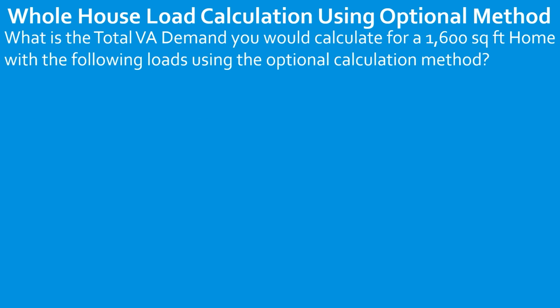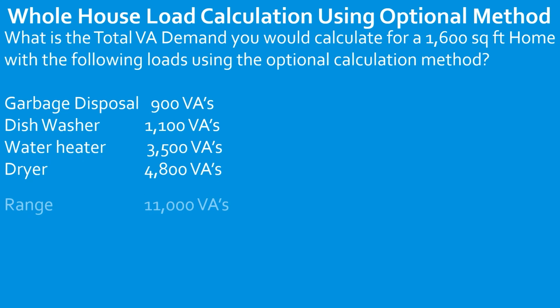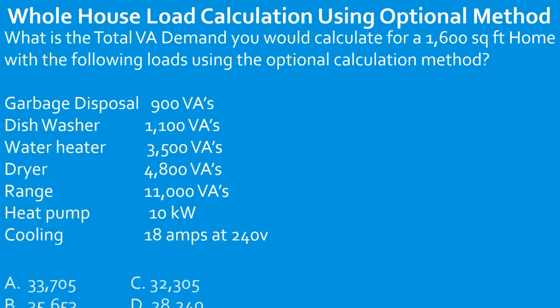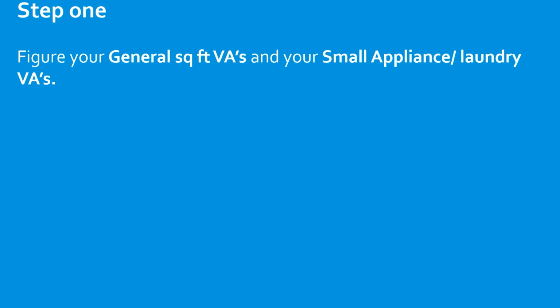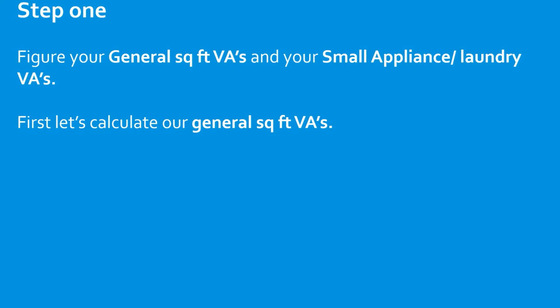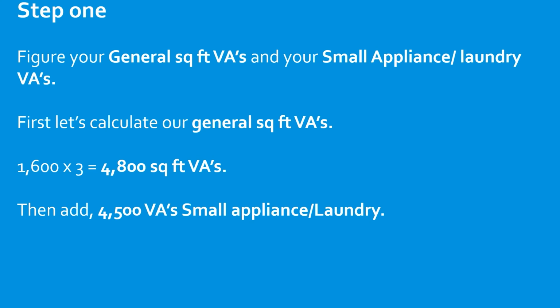What is the total VA demand you would calculate for a 1600 square foot home with the following loads using the optional method? Garbage disposal, dishwasher, water heater, dryer, range, heat pump, cooling, and we've got some options. Step 1, you always figure your general square foot VAs and your small appliance laundry VAs. First, do your general square foot VAs. So 1600 multiplied by 3 VAs per square foot, and you're going to get 4800 square foot VAs. Then you're going to add your 4500 VAs for your small appliance and laundry circuit.